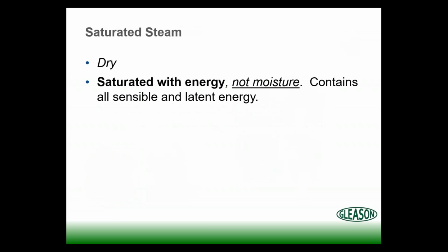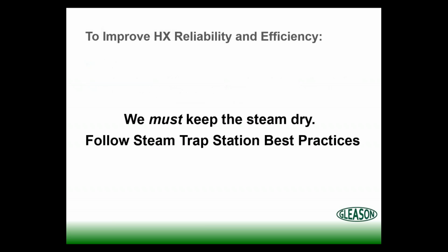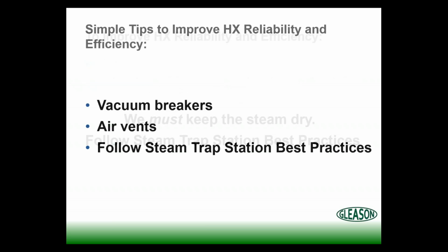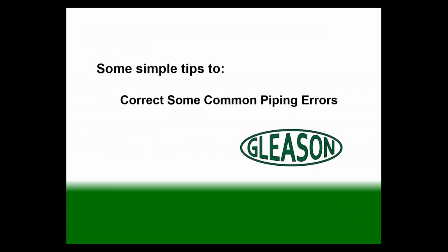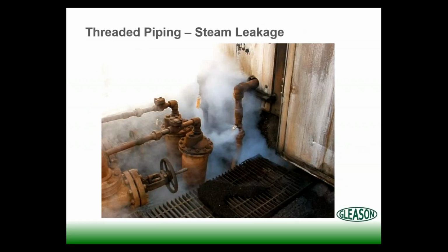So a very misused term in the steam world is saturated steam. Saturated steam is dry. It's not saturated with moisture, it's saturated with energy. And again, it's our job. We've got to keep the steam dry. So we want to follow our steam trap station best practices, use our vacuum breakers and our air vents on our heat exchangers. So real quick, some simple tips to correct some common piping errors that we see all the time.